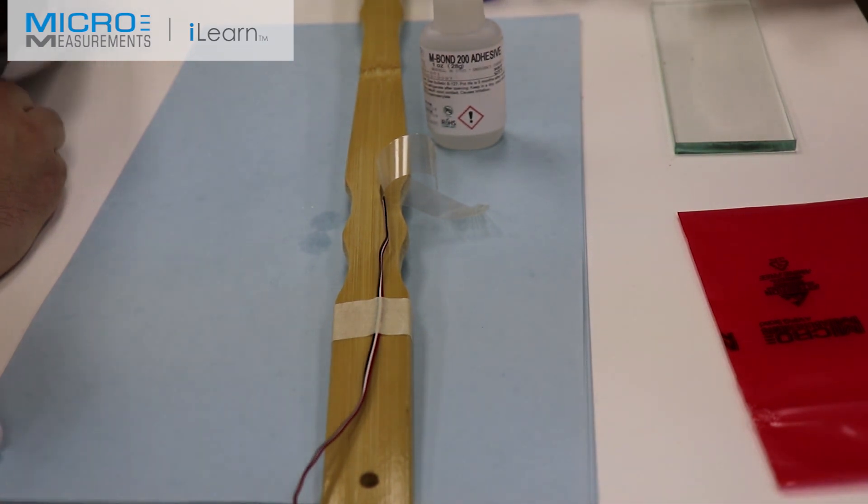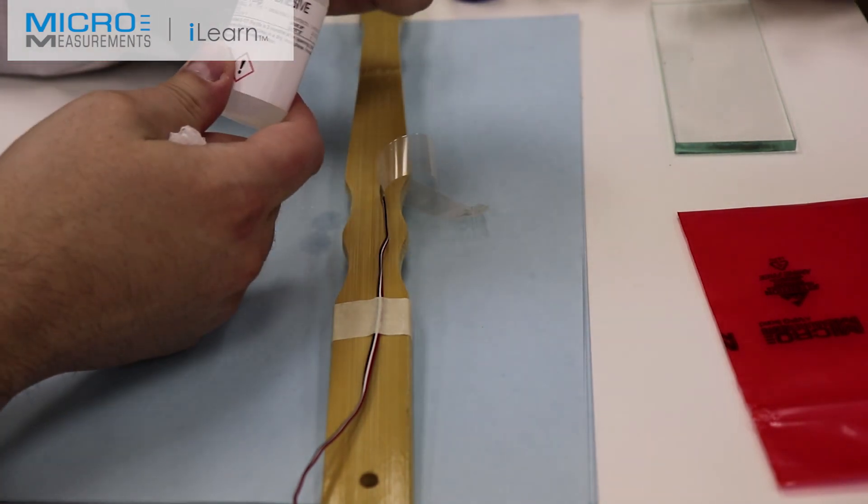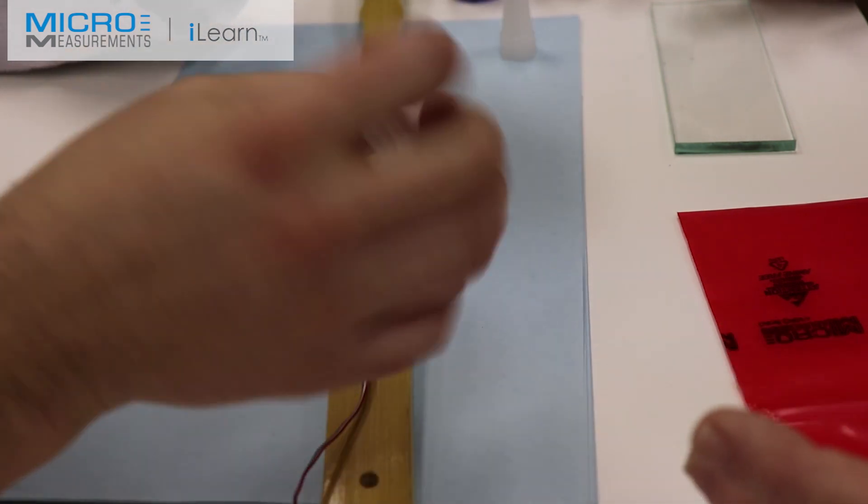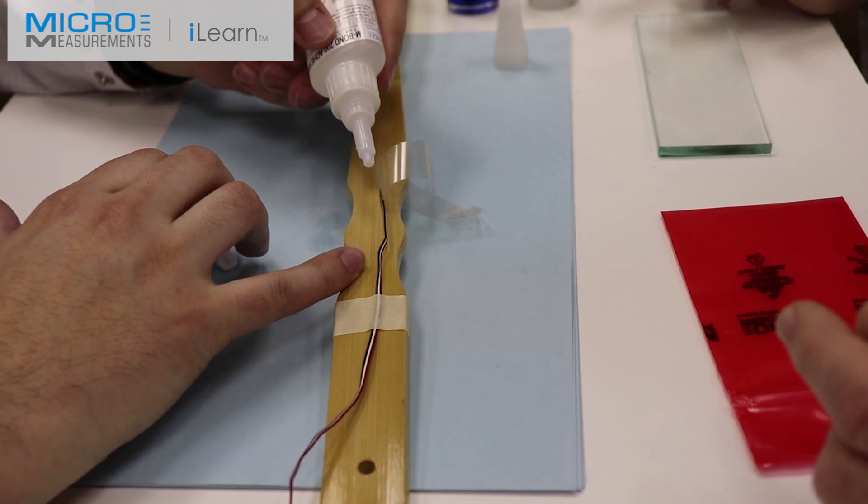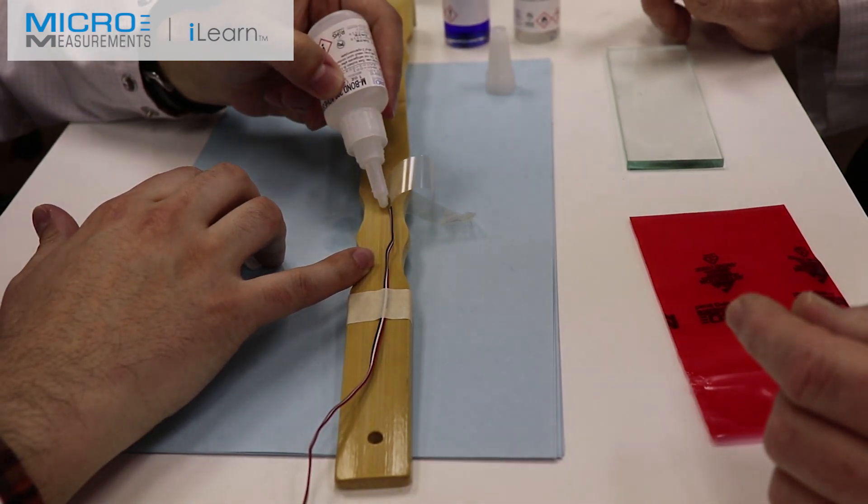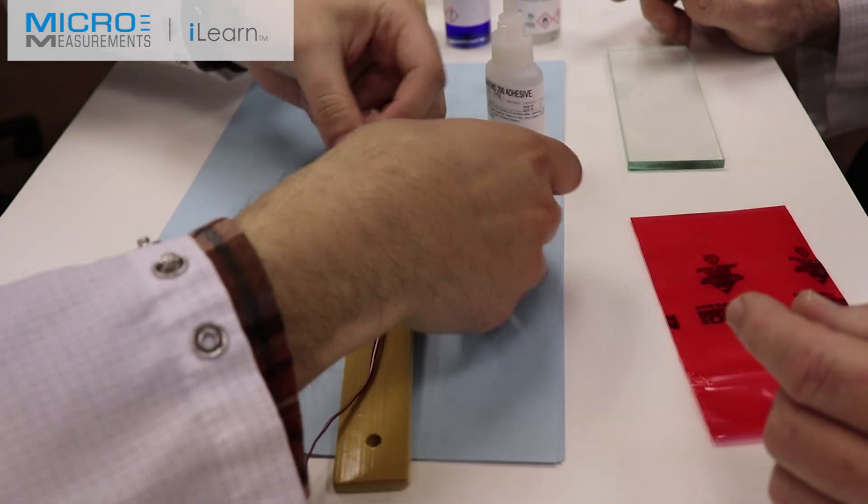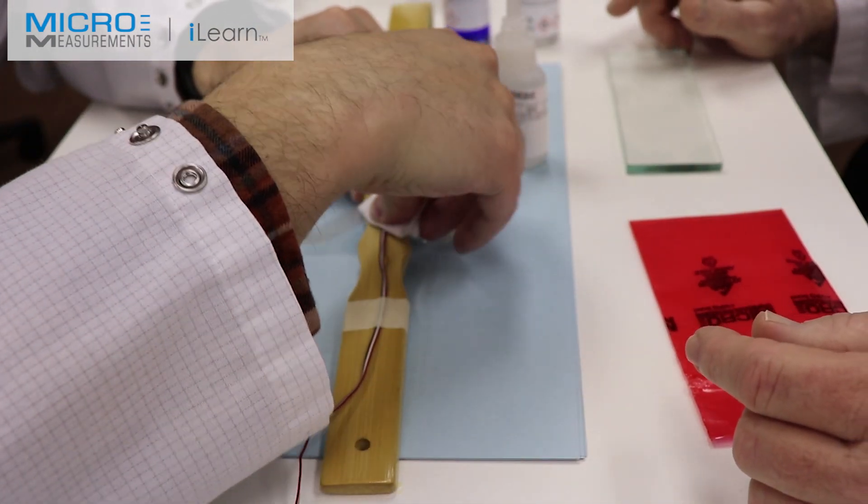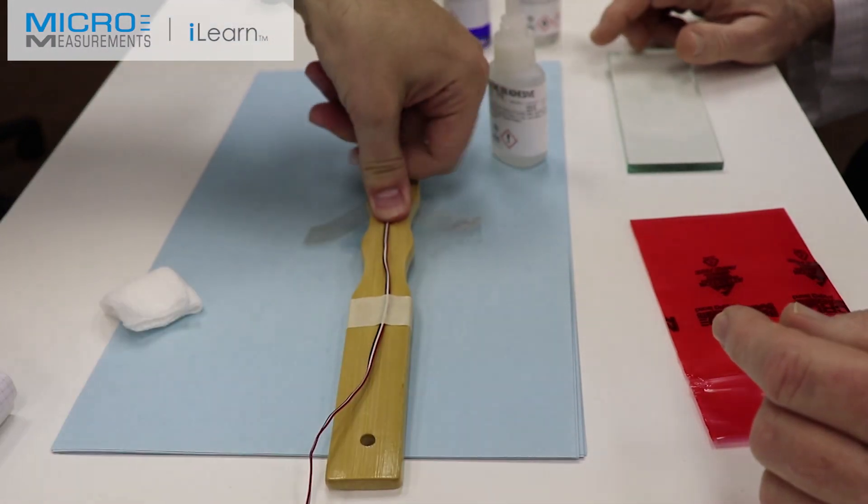We need to apply the M-Bond 200. Colin's going to open up the bottle. He's going to have a gauze sponge folded in quarters and ready for spreading the adhesive. He'll put a single drop of adhesive at the cusp of the tape and the scratcher. Then he'll take the gauze sponge, squeegee it across, and then follow with his thumb.